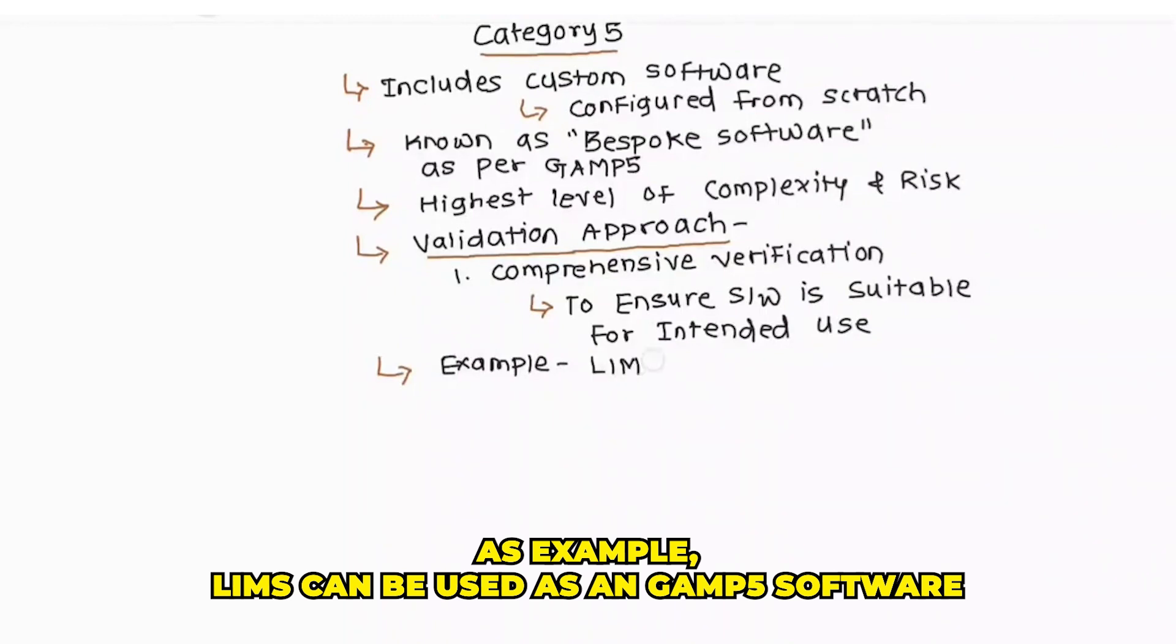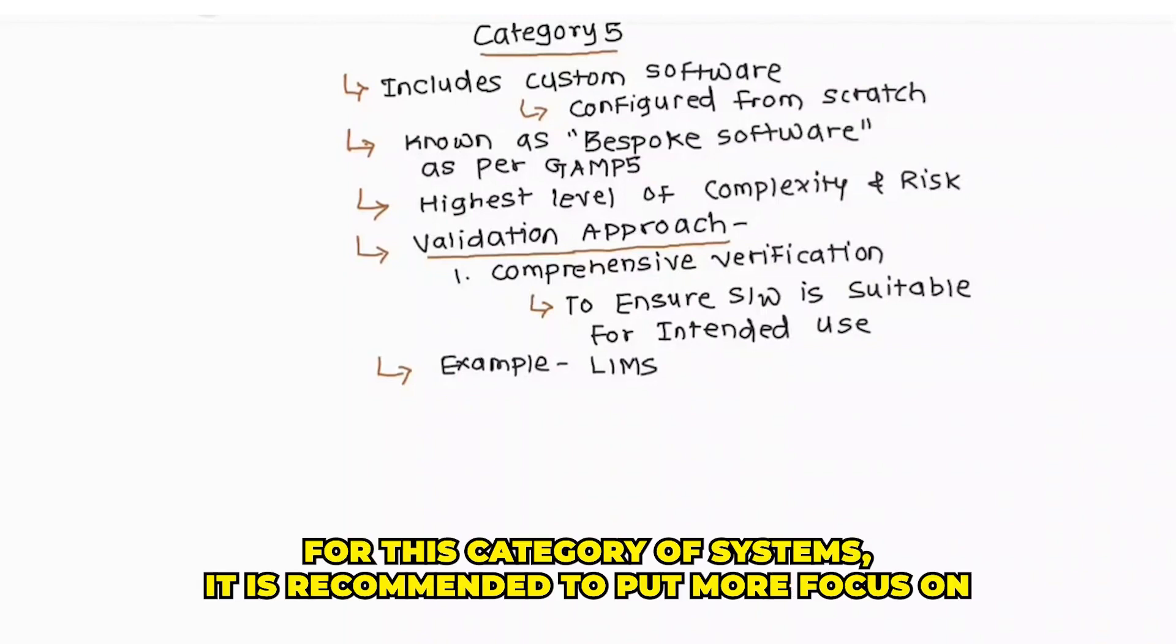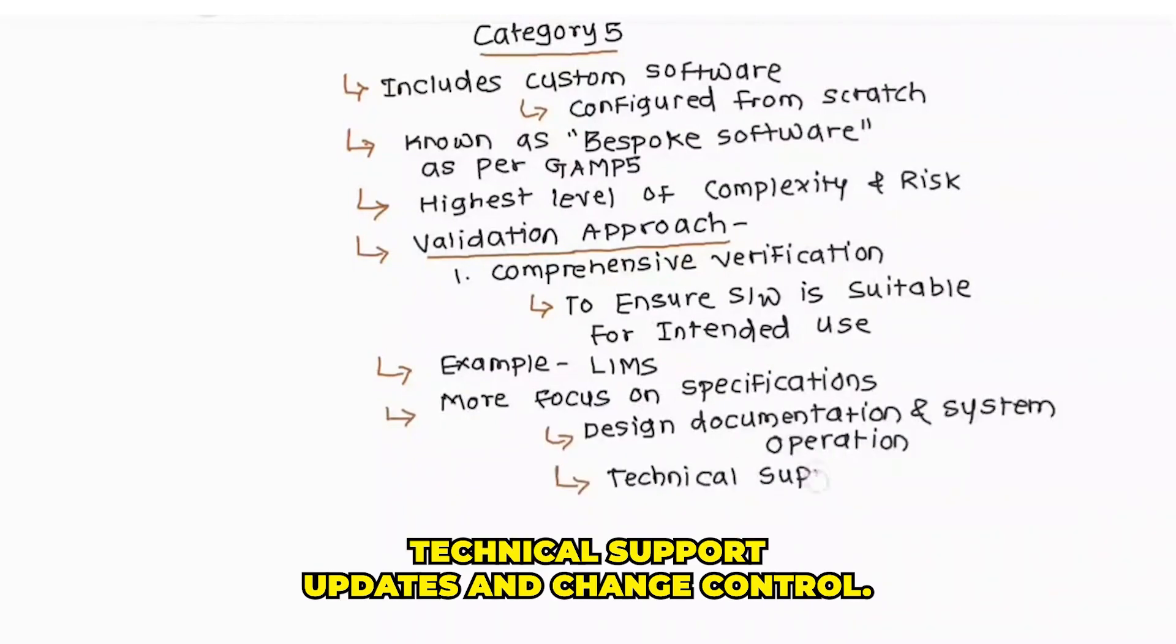For example, LIMS can be used as a GAMP 5 software. In the validation strategy for this category of systems, it is recommended to put more focus on specification and testing modules, design documentation and system operation, technical support, updates, and change control.